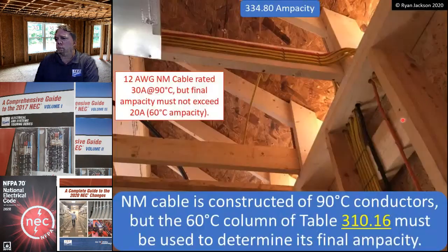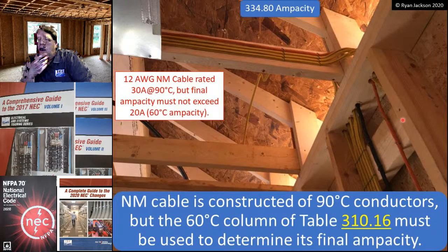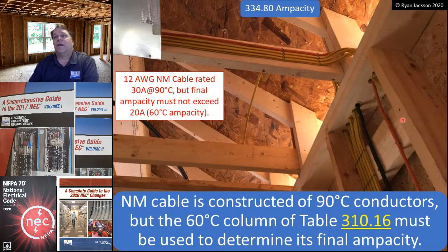334.80 ampacity. All right. NM cable is constructed of 90 degree C conductors. Has to be. But the 60 degree column of table 310.16 must be used to determine its final ampacity. So for example, here I've got these beautiful, and they are beautiful, 12-2 cables. If I go to 310.16, they are in fact rated 30 amps. However, we're going to pretend that they're only good for 20 amps, because that's what this section says. They're 90 degree wires, but pretend that they're 60 degrees.